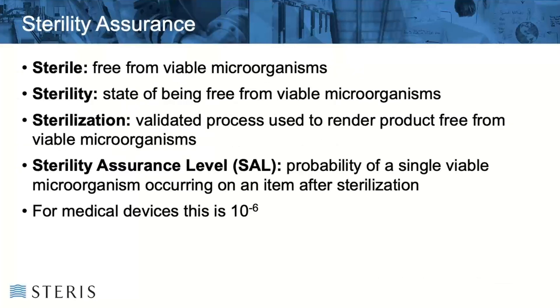So what do we mean by sterile? Simply put, it means that the device is rendered free of viable microorganisms such as bacteria, viruses and molds. Each sterilization process is designed to deliver a given amount of lethality, which is quantified in terms of the Sterility Assurance Level — the SAL. The SAL is a statistical probability of one single microorganism surviving the process. For medical devices, this probability is usually required to be one in one million, referred to as an SAL of 10 to the minus 6. All of these terms can be referenced in the latest version of ISO 11139, which gives all the terminology and definitions associated with our industry.